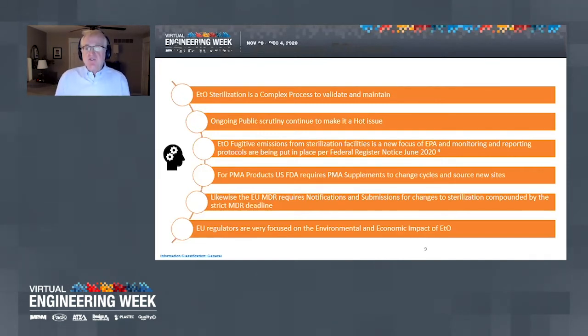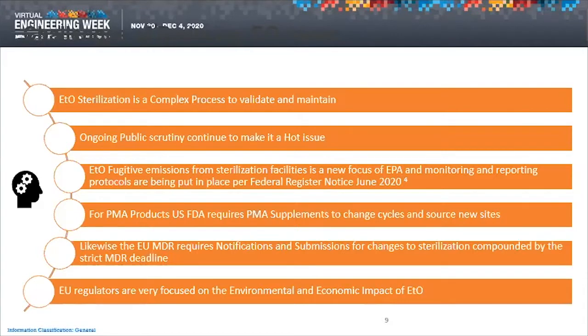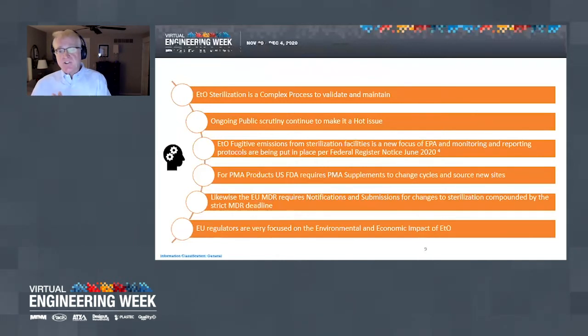And of course, this precedes the soon to be updated regulation and the NIOSH and all these other regulations, which I'm not an expert at, but I know it's going to be essentially zero emissions from these facilities. For FDA products and changes to the EO sterilization process, the regulation requires submissions and prior approval for changes to Class 3 PMA products. For those of you that have those products, it's a big deal. It's a very bright line between PMA and 510K Class 2 products in the US. Whereas for 510K Class 2, there is no submission or prior clearance when making these types of changes to your cycle. They can be reported under a letter to file and managed as part of your quality system.